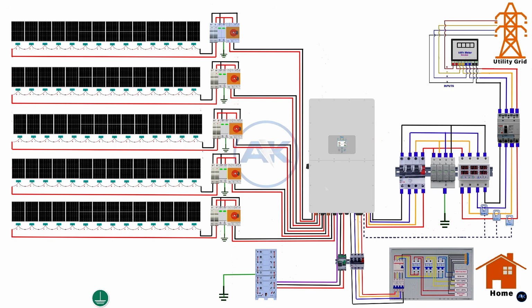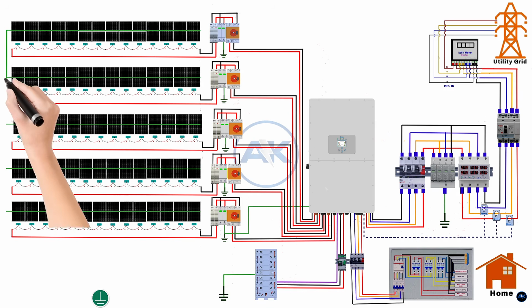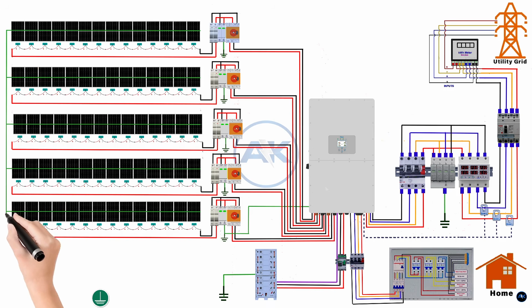Connect the inverter grounding terminal to the main grounding bar using a copper earth cable. The grounding cable must be properly sized, securely tightened, and free of paint or corrosion at the connection points. Next, ground the solar panel frames. All panel frames must be bonded together using grounding lugs or grounding clips and then connected to the main grounding bar. This protects against electric shock and lightning.